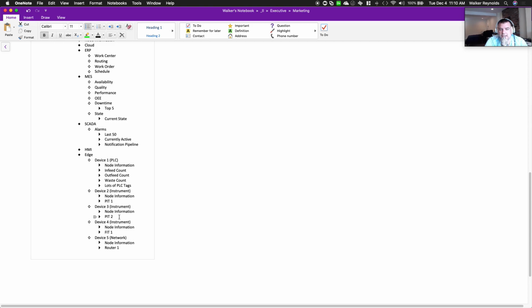Our PLC is connected to those devices, let's say over Profibus PA, because that's a super fast protocol - maybe my PLC needs that data at less than 100 milliseconds per cycle, say 8 milliseconds per cycle. You can do that over Profibus PA. So the connection between the PLC and the instrumentation on the plant floor may be a non-IIoT protocol for high-speed reasons. But in our namespace, the instrument not only connects to our PLC, it also connects to our namespace, which all of our software would consume from, and all of our decision makers would get their information from.